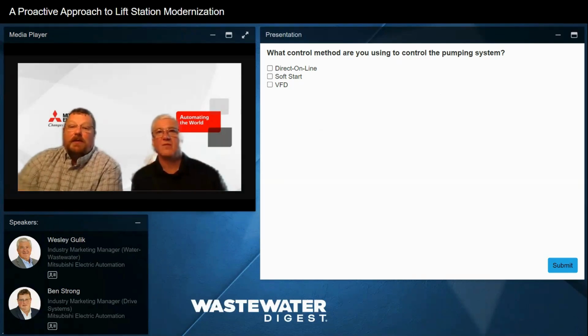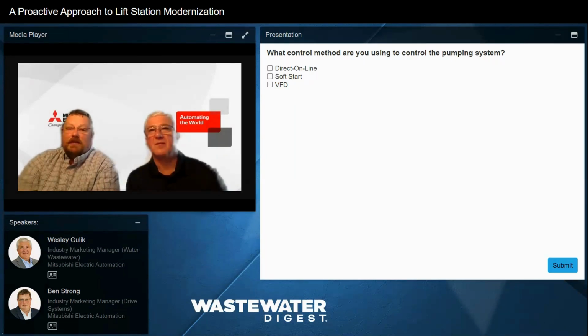So another poll: what control method are you using to control your pumping systems? I'm always surprised how many people are using direct online starters. I'd be curious to learn, are we using direct online because we have single phase input, or are there other reasons? It's what we have. It works. We don't change it out. I understand it. I'm curious to learn. Yeah, so the results, if I could read them off. The first one, the direct online, we're looking at about 39%. Soft start is 41, very, very close. But variable frequency drives are used at 58%. So it seems like the majority of the systems out there are VFD, but it varies from region to region, percentage-wise.